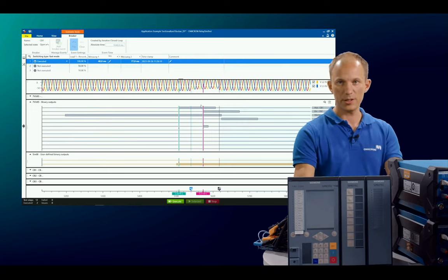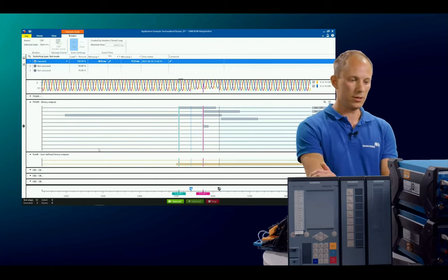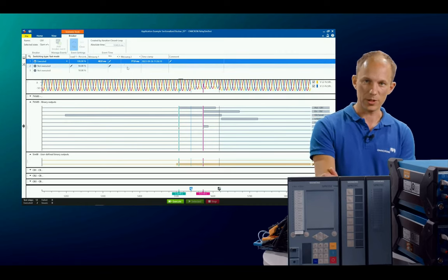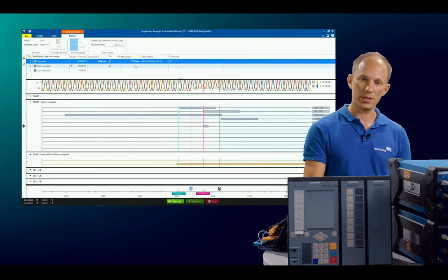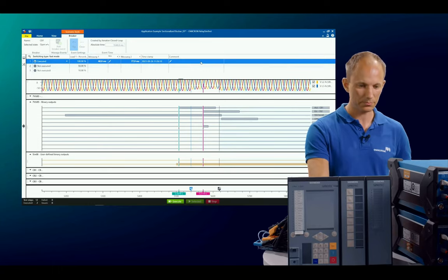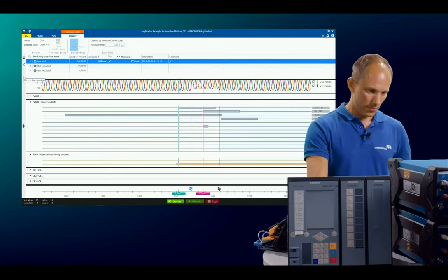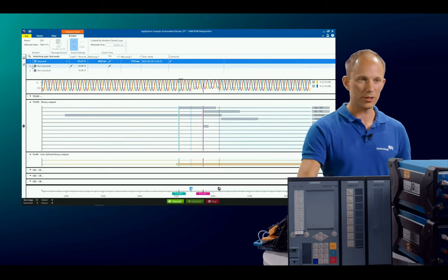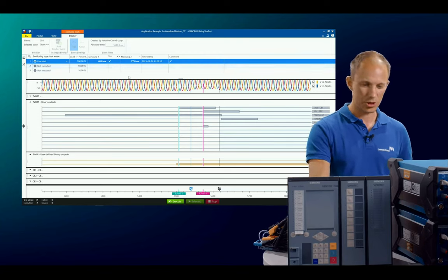These are now the signals of the relay. I could also measure the auxiliary contacts of the circuit breakers to get there this time. I have the ability now also in RelaySimTest to measure these signals and then to assess them. I can do that after the tests. Yeah, you see with the digital twin, it worked. So maybe we did something wrong in our wiring. We need to double check that.